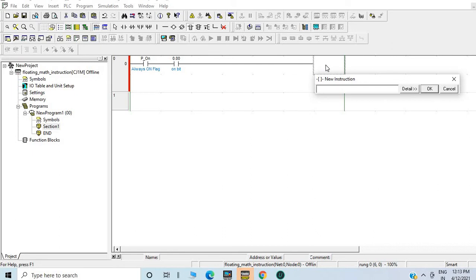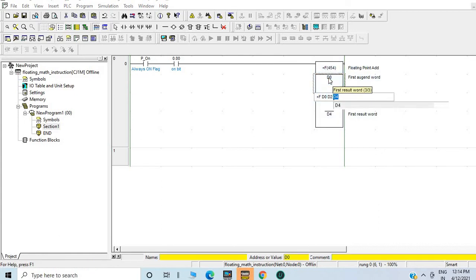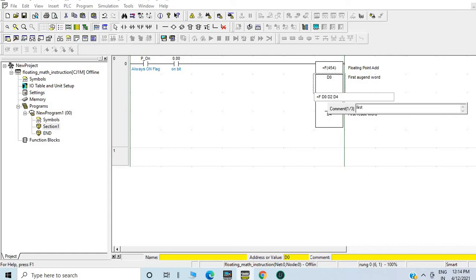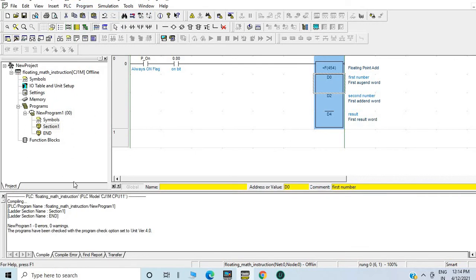I will select the floating point math instruction — floating point math instruction. I need to select PLUS F. Suppose I am taking D0, it is a double word, so I need to take D2, and I am saving the result in D4. Click OK. I will give comments: first number and result. This will do the addition. Now we will go to compile.